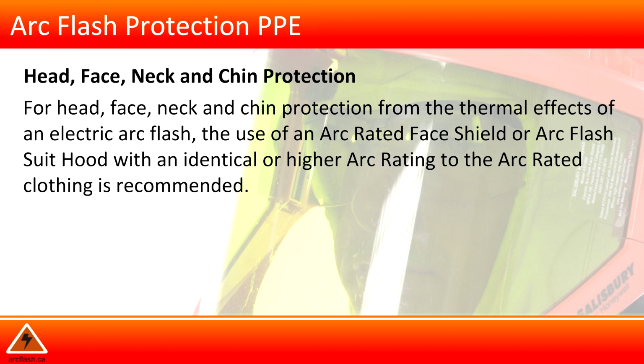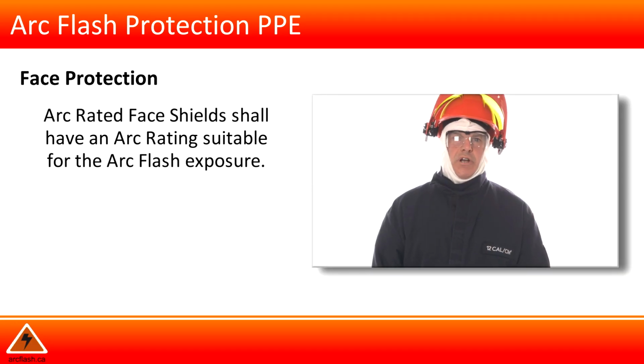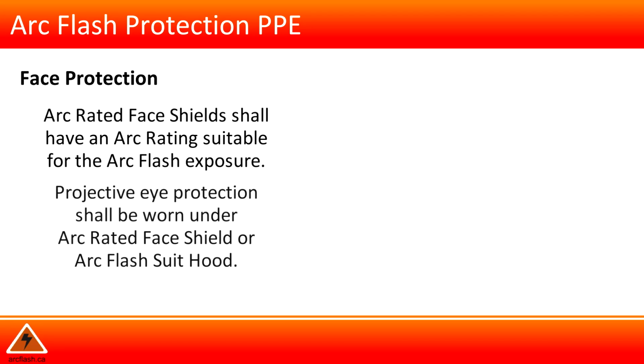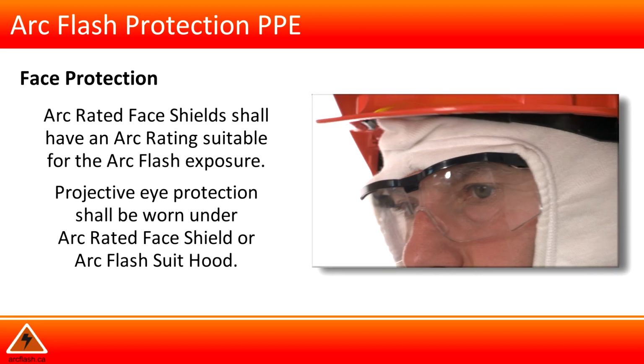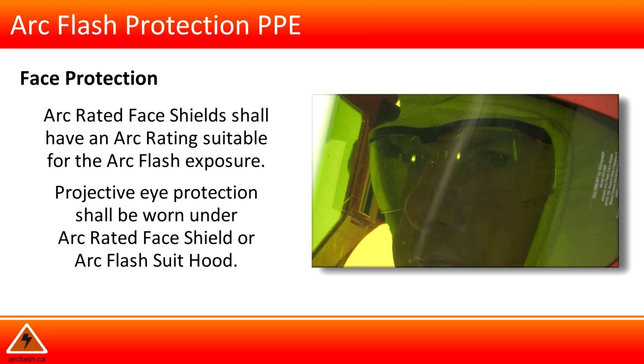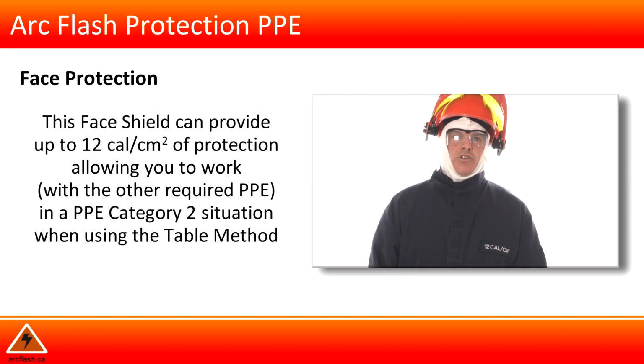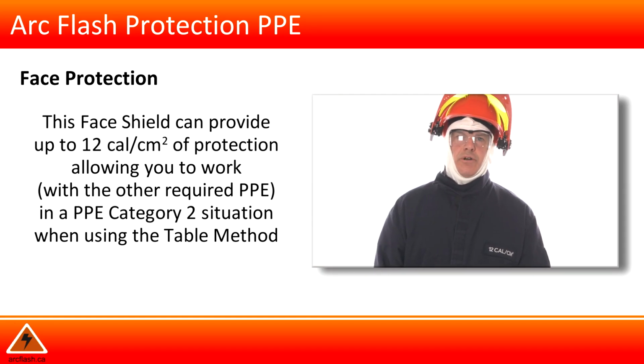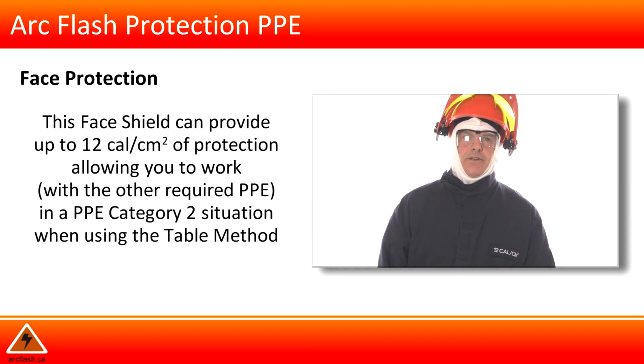The head, face, neck, and chin are protected by an arc-rated balaclava or sock hood and a hard hat face shield combination. For face protection, an arc-rated face shield shall have an arc rating suitable for the arc flash exposure. Protective eye protection shall also be worn under an arc-rated face shield or arc flash suit hood. The face shield can provide up to 12 calories per square centimeter of protection, allowing you to work with the other required personal protective equipment in a PPE Category 2 situation when using the table method.